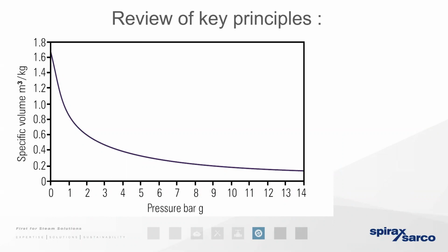in volume. So just to remind ourselves, if we're generating steam and distributing steam at a pressure of 10 bar gauge, well, we know that that's going to have a volume slightly below 0.177 cubic meters. But then again, if we've reduced the pressure of the steam at the process from 10 bar gauge to 2 bar gauge, we know that the volume is going to be considerably larger. But we also know that when steam gives up its latent heat, we're left with that sensible heat in the condensate. And that's going to exist at the same temperature and the same pressure as the steam itself. So when the condensate falls in pressure, when it passes across a steam trap, for example, that release of excess energy is being converted from sensible heat back to latent heat. That's what's going to result in that phase change. And that huge expansion is one of the reasons why we so often need to vent that flash steam away, at which point it becomes lost because it's vented to atmosphere.